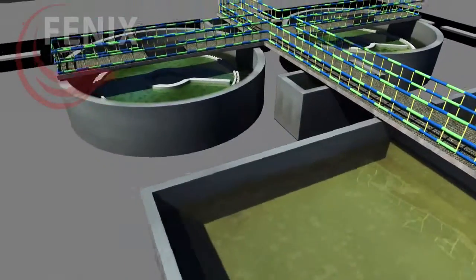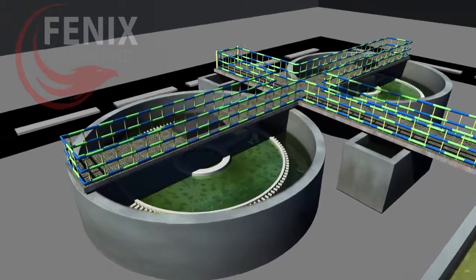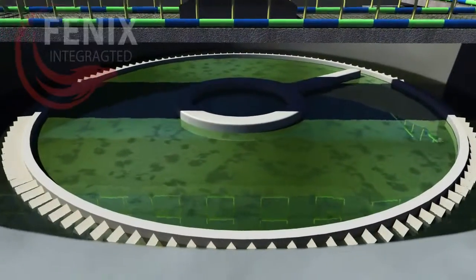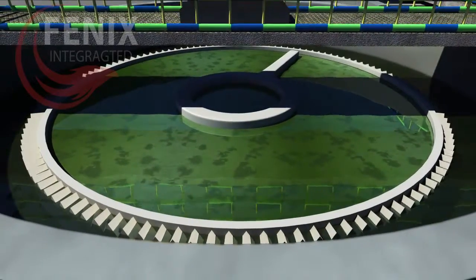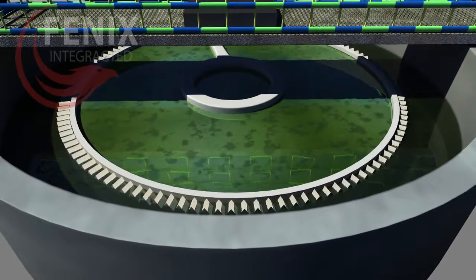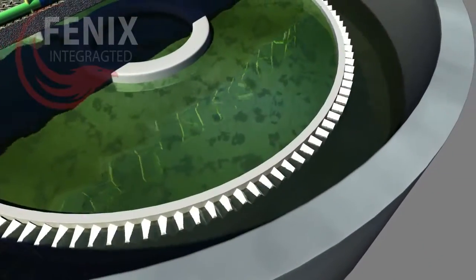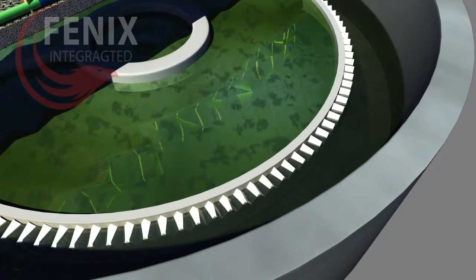We are now ready to move to the secondary clarification. Just like in the grit and grease removal tank, the water goes into a big tank and sits. Now all the bugs and other sludge sink to the bottom, but some of these bugs are pumped back to the biological treatment tank. These pumped back bugs will be used to eat the bacteria out of the new incoming wastewater and to reproduce more bugs so that the plant never runs short of bugs. Bugs are essential for the wastewater treatment, as without them we can't clear the wastewater from those dangerous bacteria that come with it.